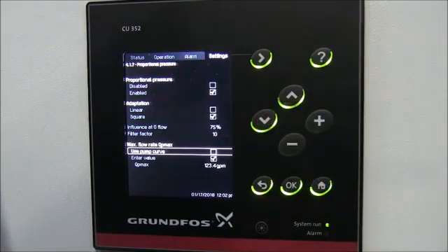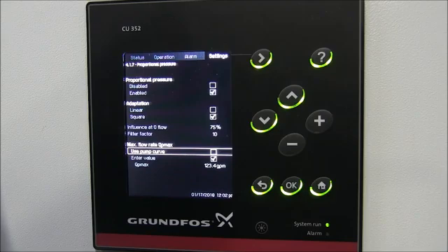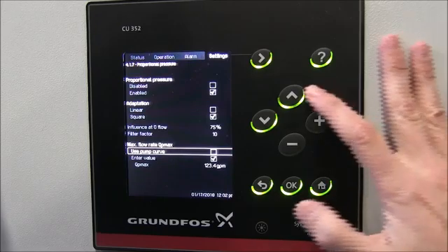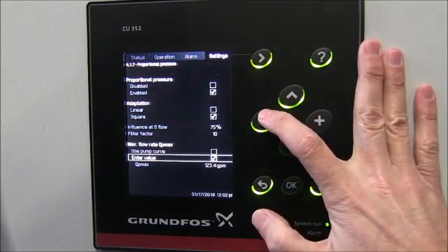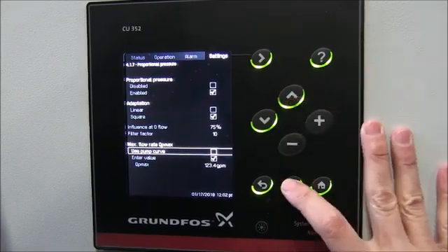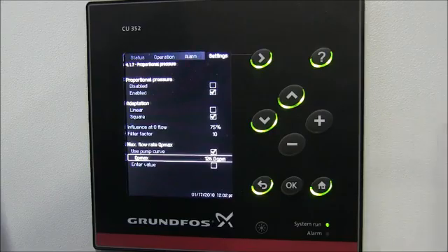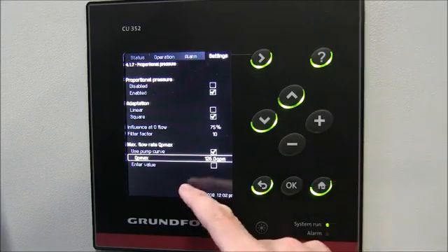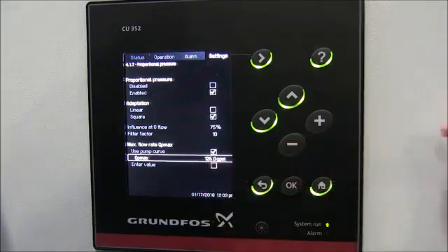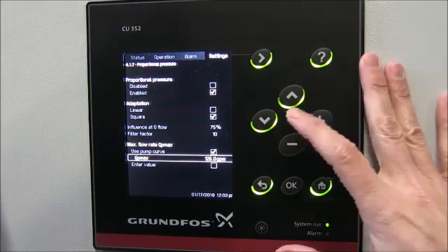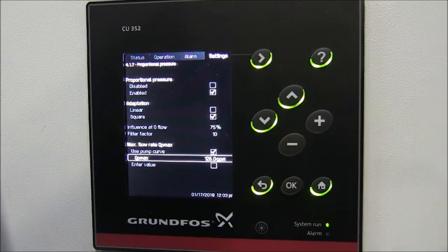For the max flow — QP Max — we're going to use the pump curve to establish it. Three pumps running at 100 percent will result in a max flow rate that the controller can calculate for us. With our current set point and the three pumps on this system our max flow is about 126 GPM, because our pump curves are loaded into the controller.